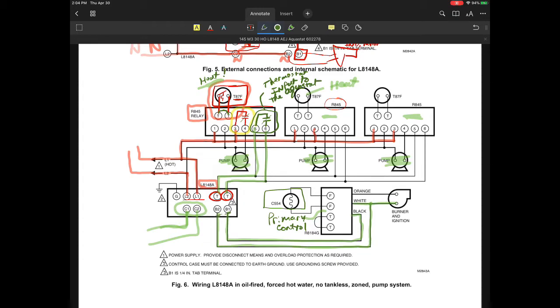On that primary control, you've got a CAD cell, which is really a light sensor to detect a flame. The way those work is if I energize B1 and B2 and I say, hey, I want this burner to run, assuming the burner lit off, this will see light and it'll give you a very low resistance to complete the path for F and F. And when that's low resistance, that'll allow the heating or the safety circuit to be removed from stopping the burner from running if there is a problem. So that's what it does on here to some extent. We certainly wouldn't jumper this out unless we were trying to do some field diagnosis, but typically that's how that works.